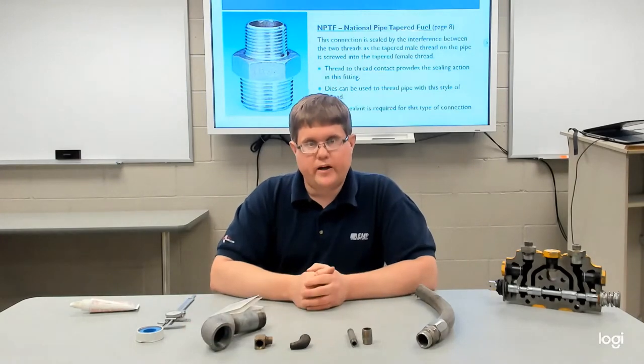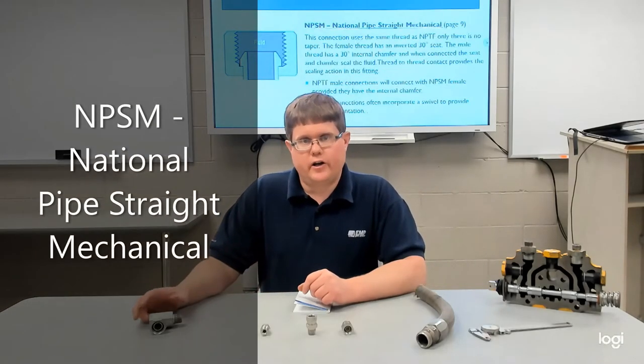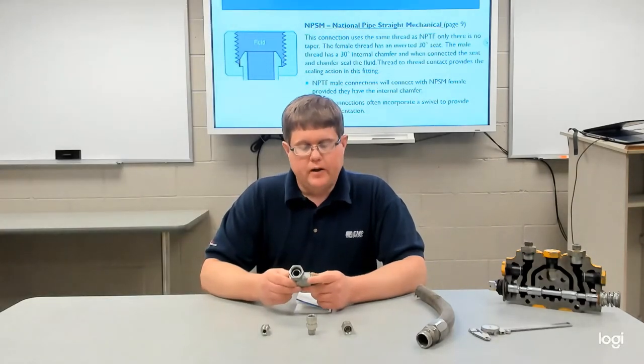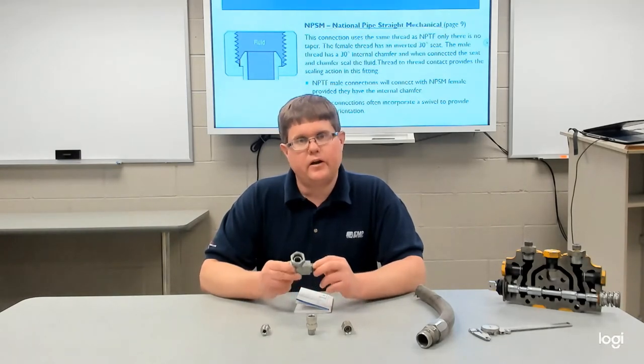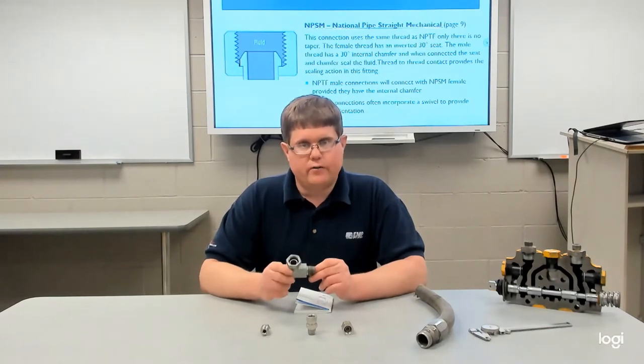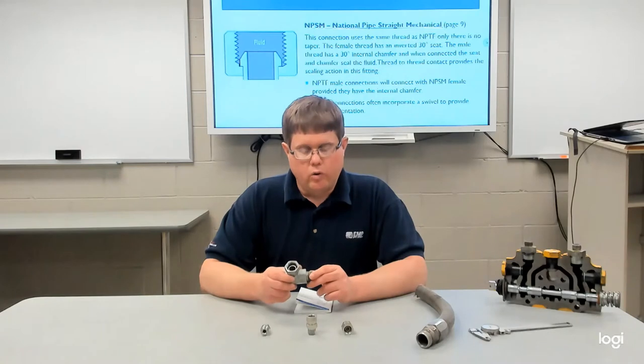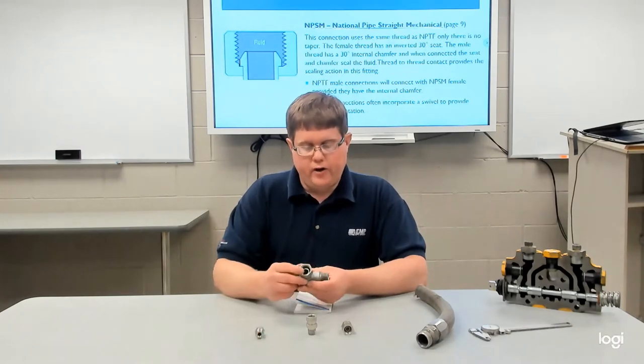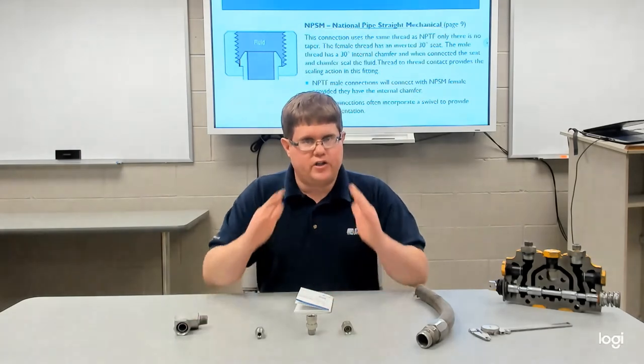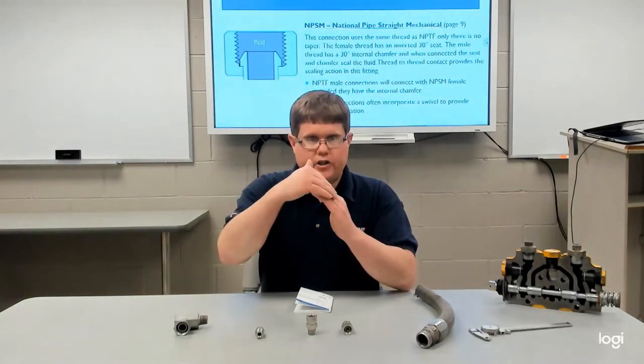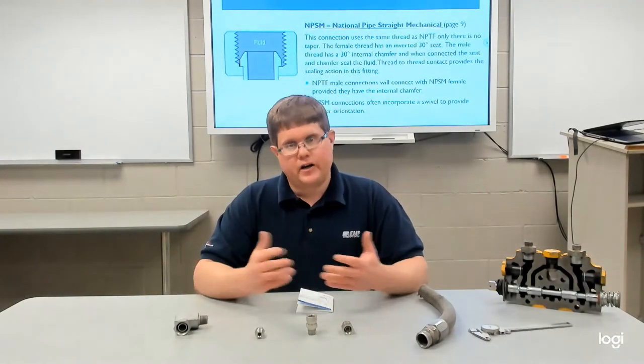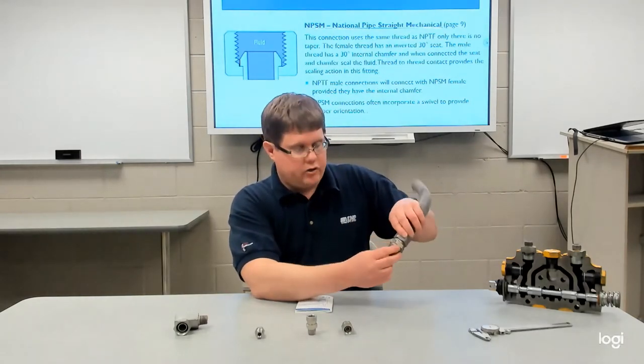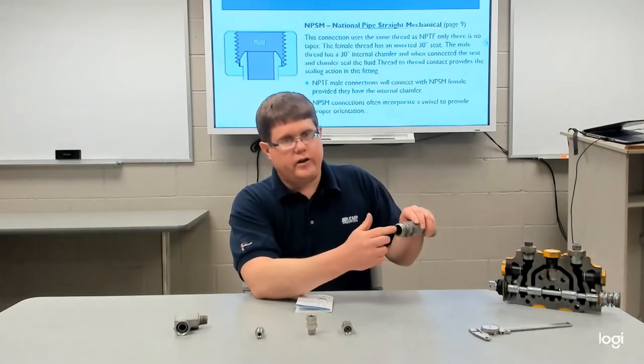The next hydraulic connection is NPSM, National Pipe Straight Mechanical. It is very similar to pipe thread in dimensions, except the pipe doesn't need to be tapered — it can be straight. The difference is that the threads no longer do the sealing. The male connection has an internal chamfer, and the female connection has a raised cone-type seat at 30 degrees that seats with that chamfer to create a sealing surface. Some pipe thread connections can be used for either NPTF or NPSM — if there's an internal chamfer, it can seal with NPSM.